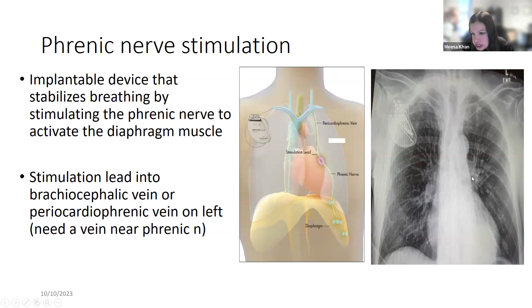It comes on automatically. So there are three things that have to be in place. It has to be a scheduled time when the patient is asleep. The patient has to be in a reclined position. So there are position sensors in the device that can tell what we call pitch, and we set what pitch the patient needs to be below for the device to turn on, and they have to be not moving. So when all these three things are in place, the device will turn on. In the middle of the night, the patient can pause therapy if they sit up. When they sit up, the device automatically pauses. You can program this time. Most of the time we program it for 10 to 15 minutes, but the range you can program is anywhere from 1 to 30. When that time frame is up, it will reassess for all three things again.